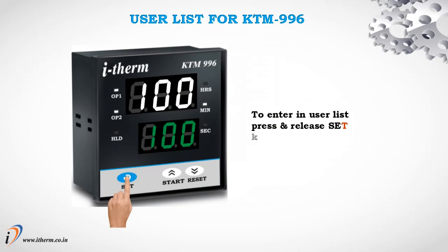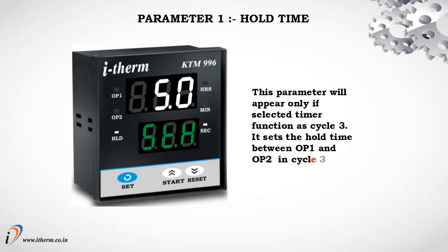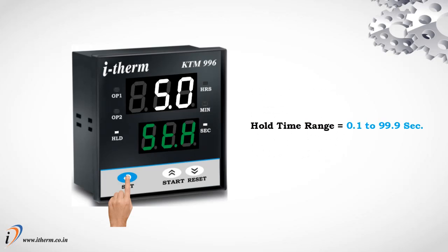User list for KTM 996. To enter the user list, press and release the set key once. Parameter 1, hold time. This parameter will appear only if the selected timer function is cycle 3. It sets the hold time between output 1 and output 2 in cycle 3. Hold time range 0.1 to 99.9 seconds.